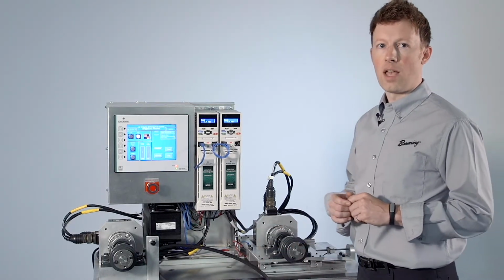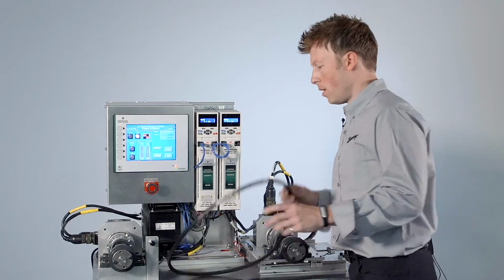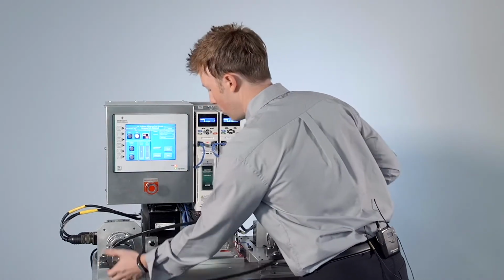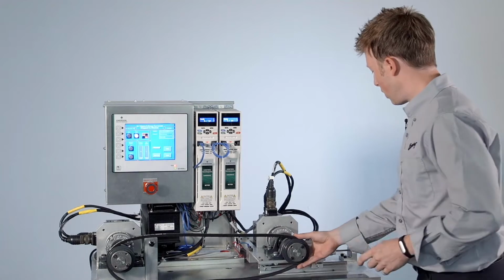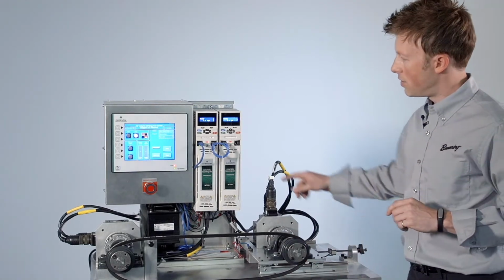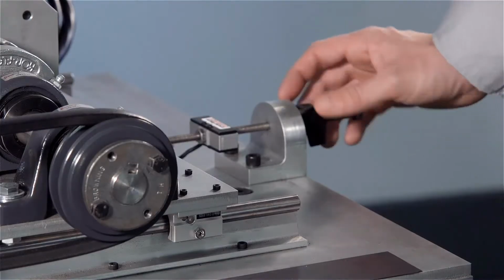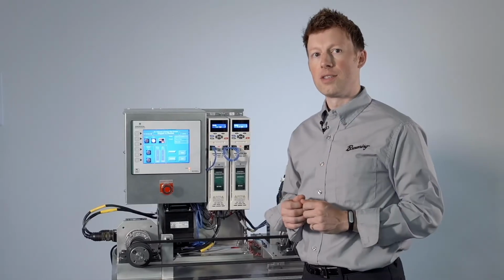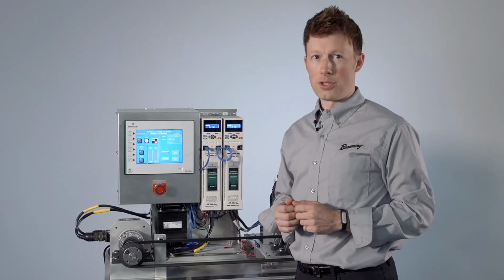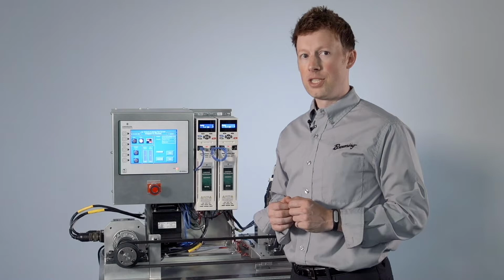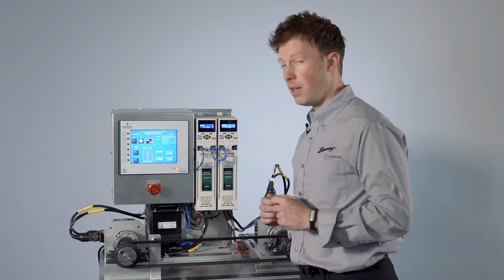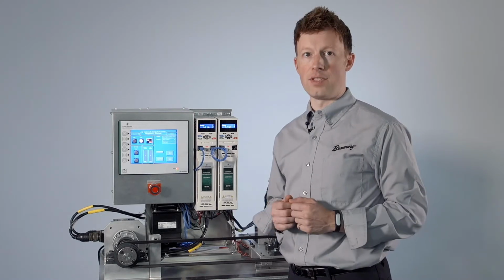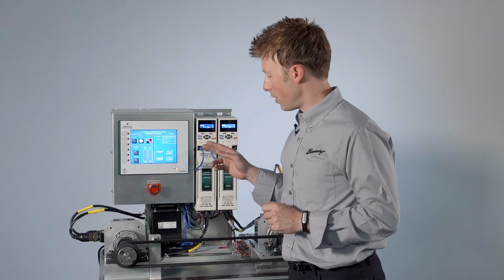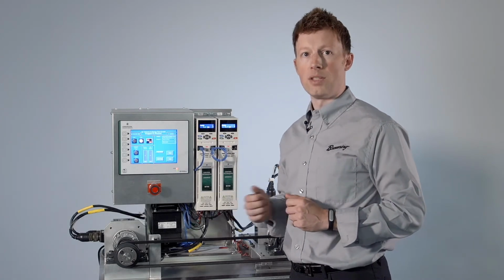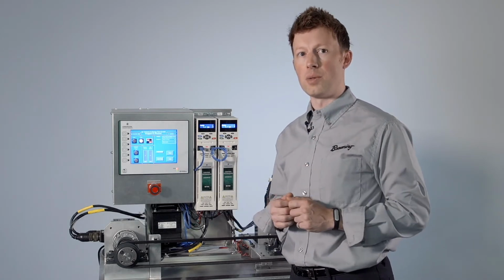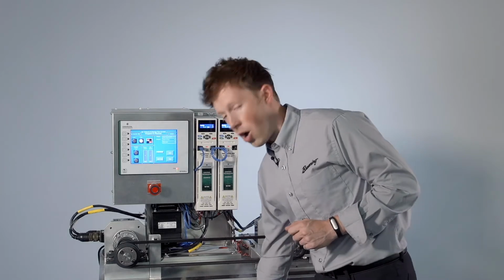So to start off, I'm going to test the wrapped belt. We're going to install it properly to a predetermined tension that we're going to check on the load cell here and seen on the screen here. From the affinity laws, the CFM, or airflow, is directly proportionate to shaft speed. So what we'll be monitoring is shaft speed and using that to calculate an effective CFM. We'll also be monitoring the kilowatt consumption of the motor and belt temperature, and then we'll compare those values against what we get from the test of the notched belt.